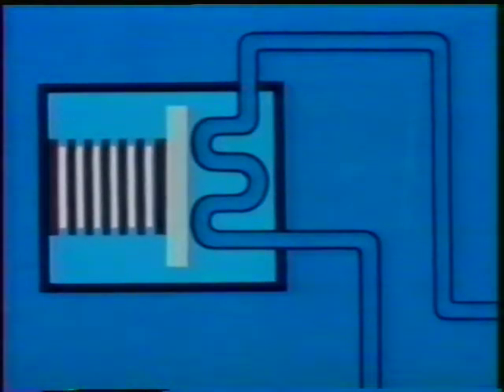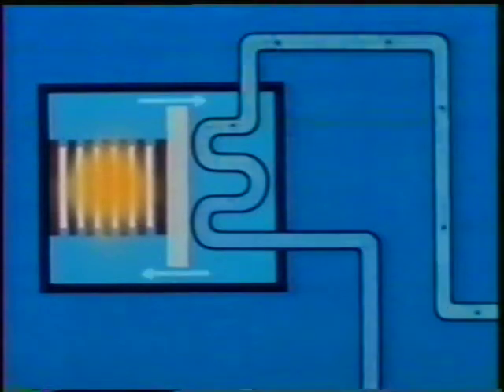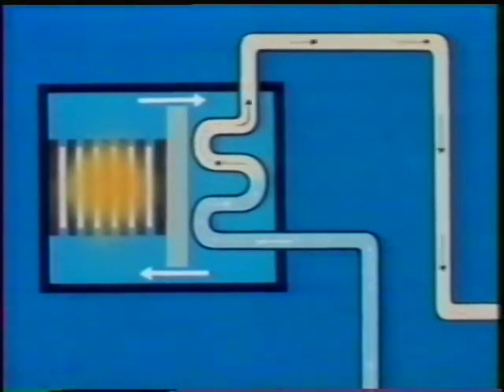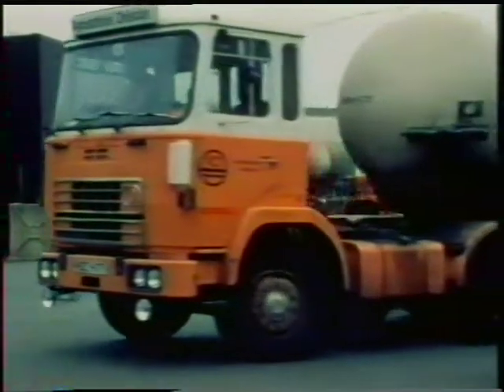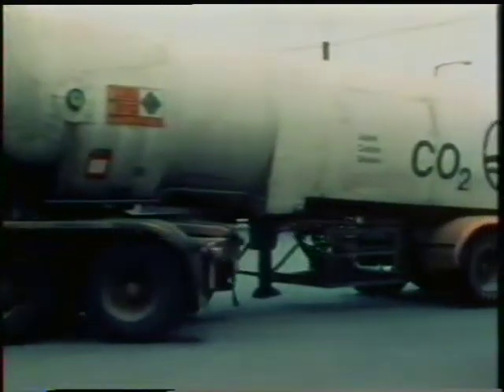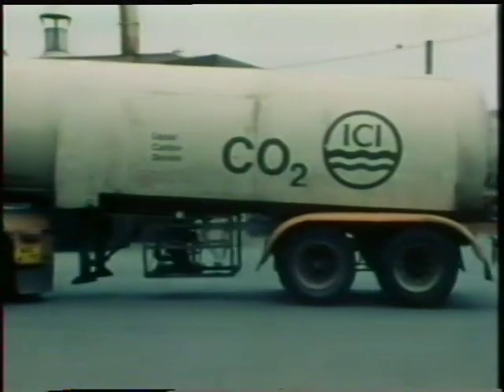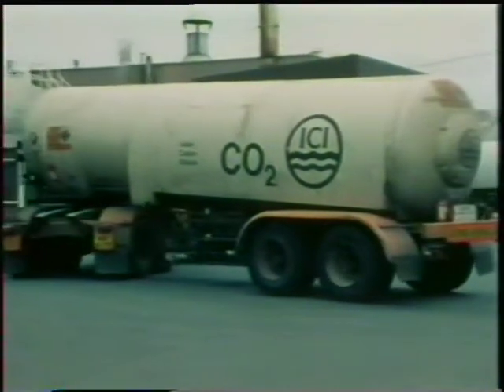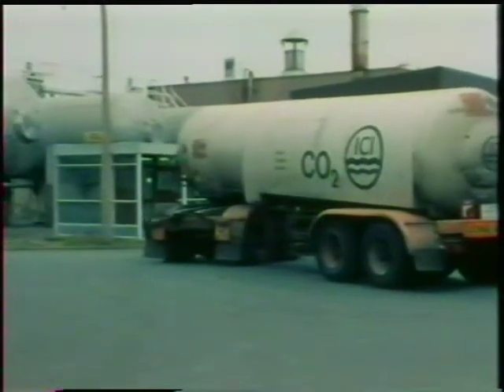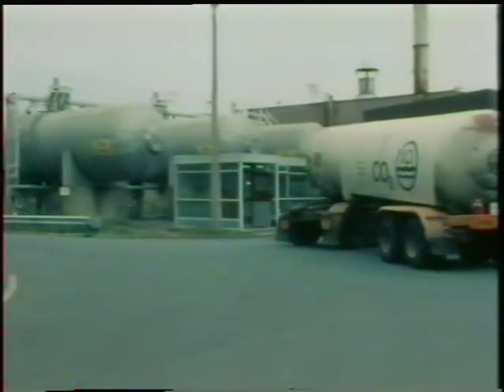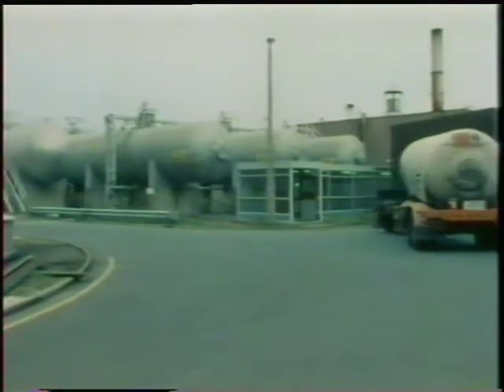Here's a simplified diagram of the boiler arrangement. There are boiler tubes through which water passes, separated by a shield from the reactor. The reactor produces heat, and gas circulates around the fuel elements, carrying the heat to the tubes, so that steam's produced and passes out to drive the turbines. The gas used to transfer heat from the reactor to the boiler tubes is carbon dioxide, CO2. It arrives at the power station in big tankers carrying the liquefied gas, and it's stored in tanks until it's needed.